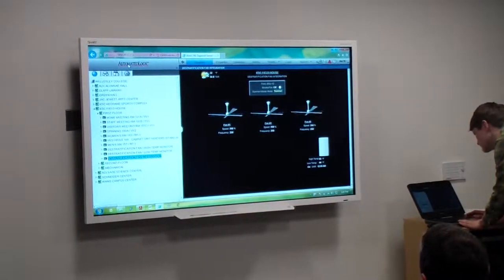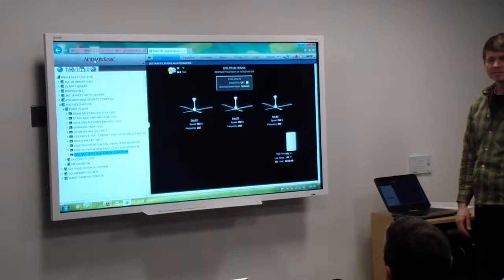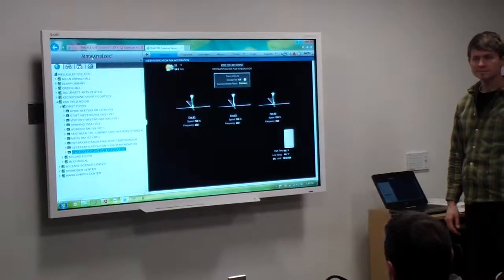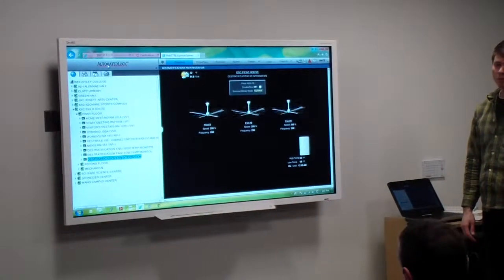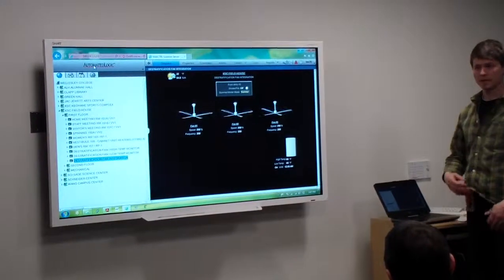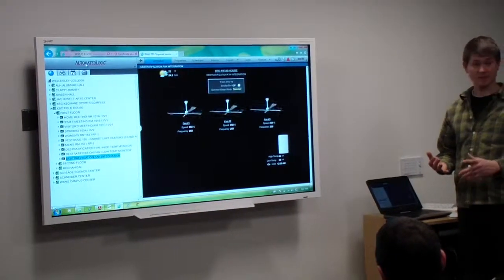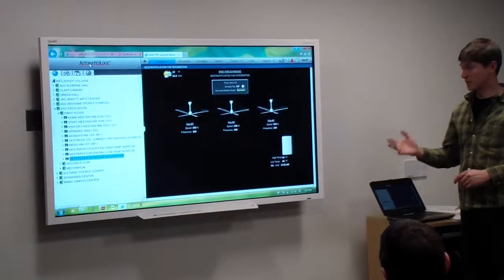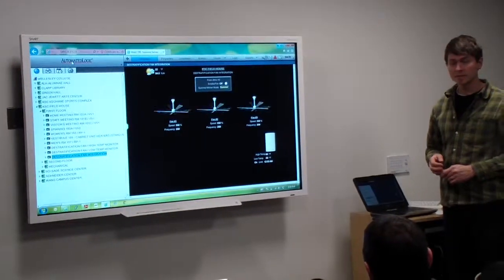So those drives, you don't have to manually go up there if you lose power or anything? It's not one of the drives that you have to go and reset? No, we've seen power go on and off while they were cycling for the different power tests that they were doing, and the units do come right back up. So that's working quite well.